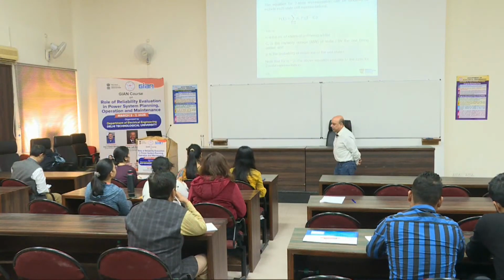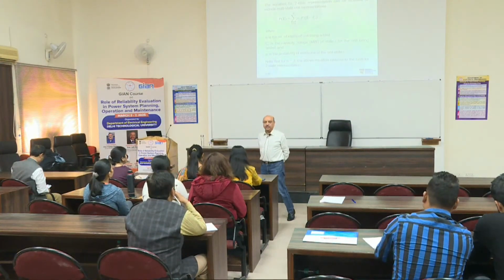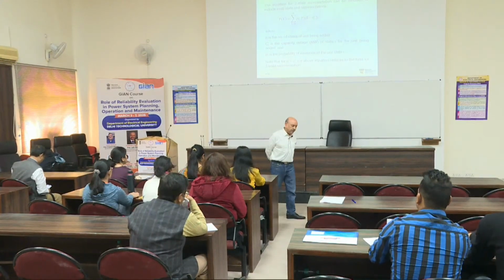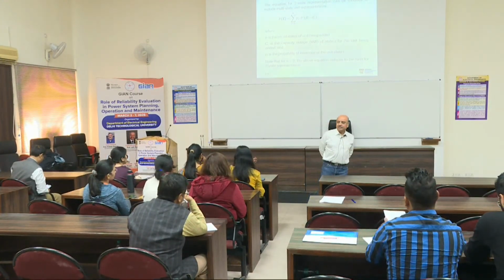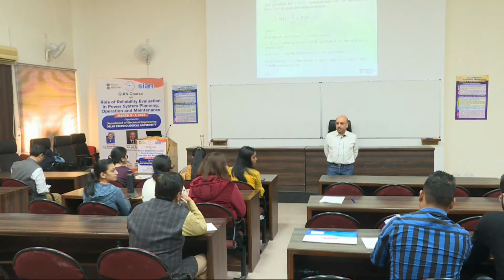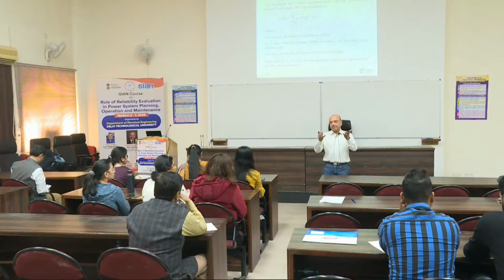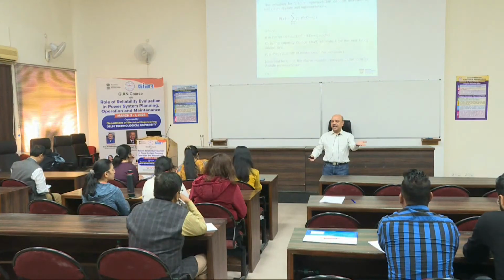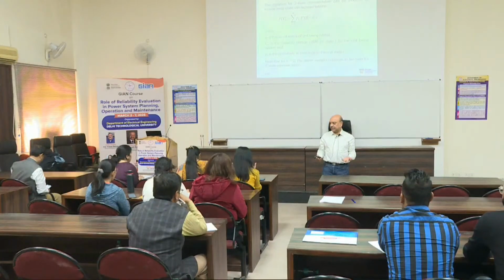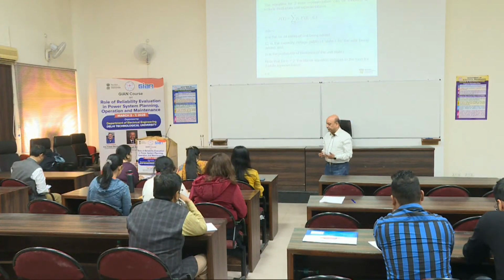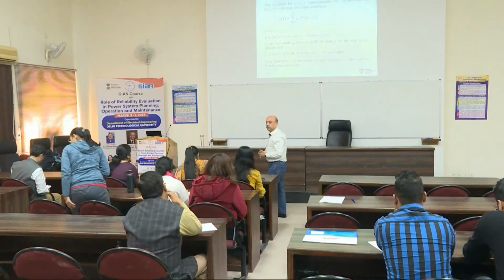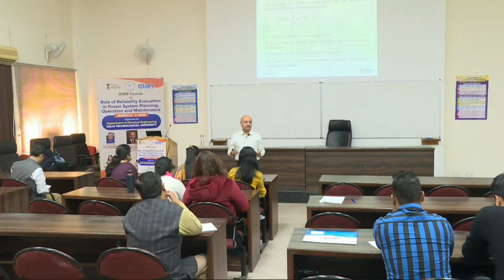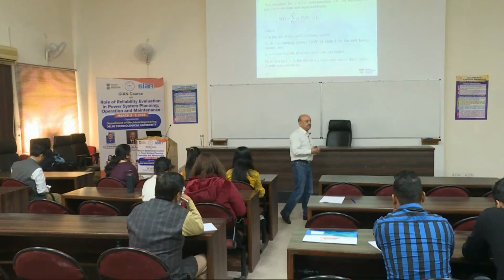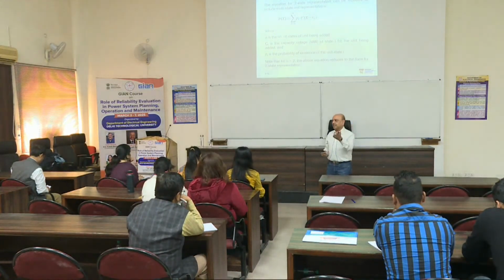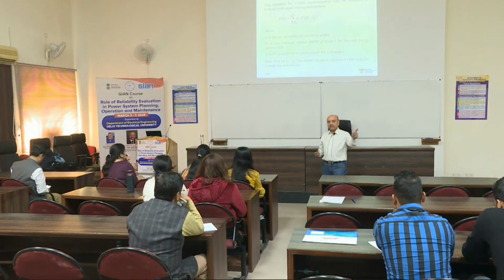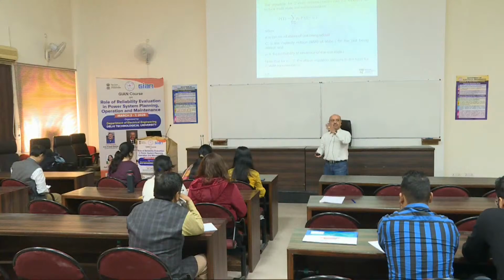So yesterday we were talking about generating capacity reliability evaluation. We started to talk about the generation model in the form of a capacity outage probability table. It's a simple table showing the capacity states and their corresponding probabilities. So it's as simple as that. We also said that instead of using state probabilities, we can use cumulative probabilities, and that is sometimes advantageous because we can directly find the cumulative probability of X or more megawatt out of service by just looking at one value rather than adding up a few values.